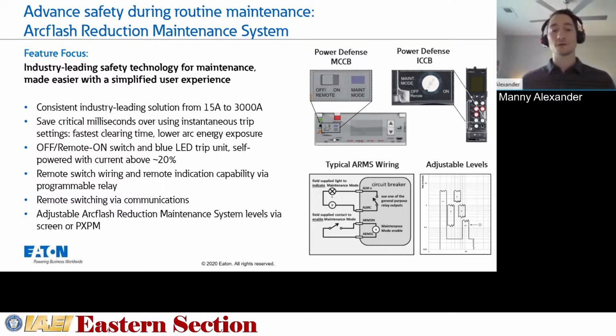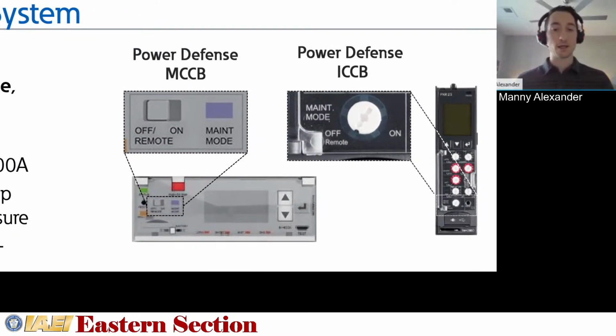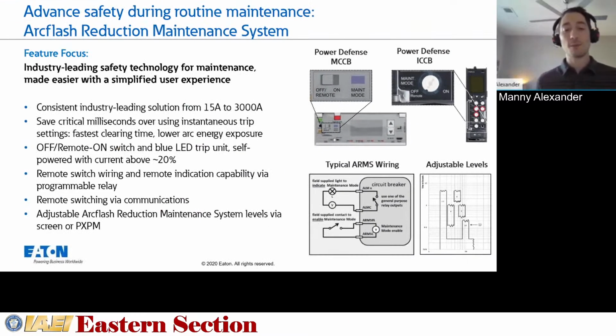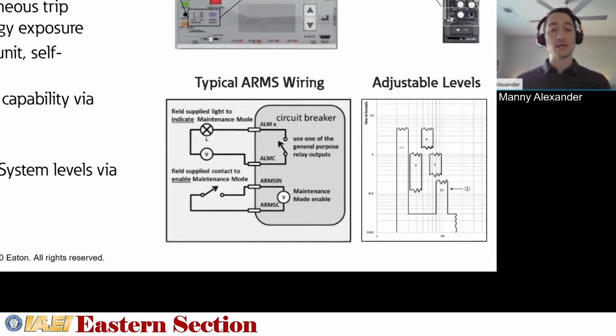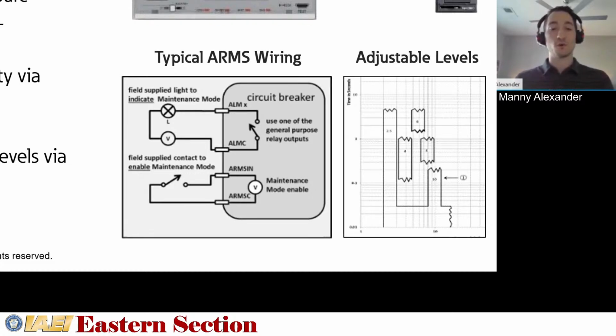So, Power Defense offers really multiple methods of arc flash mitigation, but for applications where that maintenance is performed locally at the breaker, that Eaton Arc Flash Reduction Maintenance Switch, or again ARMS, is a really great solution. If you think about an electronic trip unit's instantaneous trip setting, it's capable of clearing a fault within roughly 50 milliseconds or so. But that arc flash reduction maintenance switch uses a separate analog circuit, so that bypasses the electronic trip unit's microprocessor that requires time to boot up, perform current conversions, and execute its code. So by cutting out the need for computing time, the analog circuit can provide even faster breaker clearing time in the range of 10 to 30 milliseconds instead of that 50 milliseconds that I mentioned before, which results in a much lower arc energy exposure to the maintenance staff.